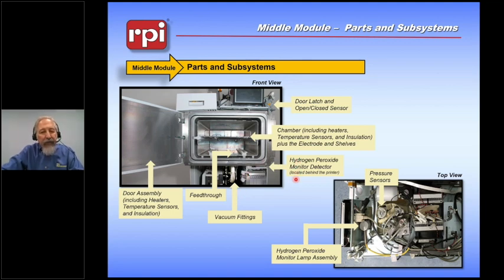One of the reasons that I'm pointing out this peroxide detector is because it's very close to the front of the machine. And if you're working anywhere within the bottom of the machine, it's very easy to hit this device. The hydrogen peroxide monitor is extremely static sensitive. You never want to unplug it while the machine is powered up. You never want to unplug it without being properly grounded, and you never ever want to unplug it while the machine is plugged in or turned on.